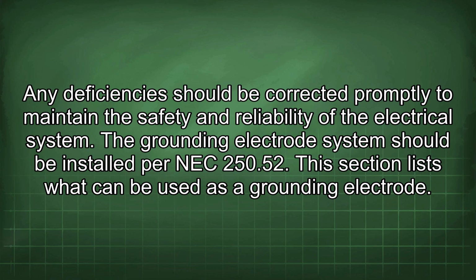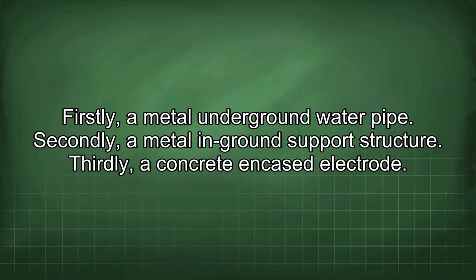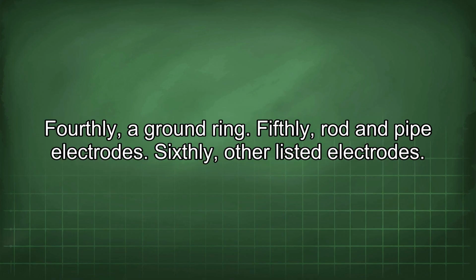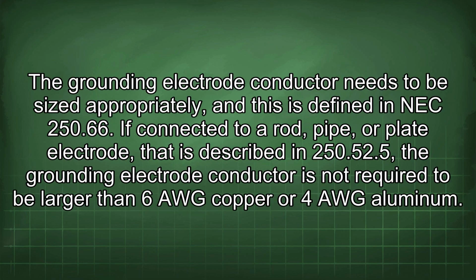The grounding electrode system should be installed per NEC 250.52. This section lists what can be used as a grounding electrode. Firstly, a metal underground water pipe. Secondly, a metal in-ground support structure. Thirdly, a concrete encased electrode. Fourthly, a ground ring. Fifthly, rod and pipe electrodes. Sixthly, other listed electrodes. The grounding electrode conductor needs to be sized appropriately, and this is defined in NEC 250.66.